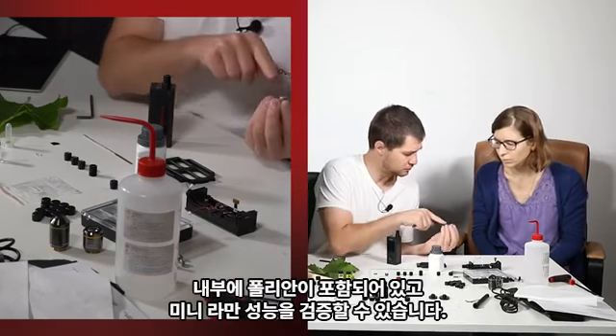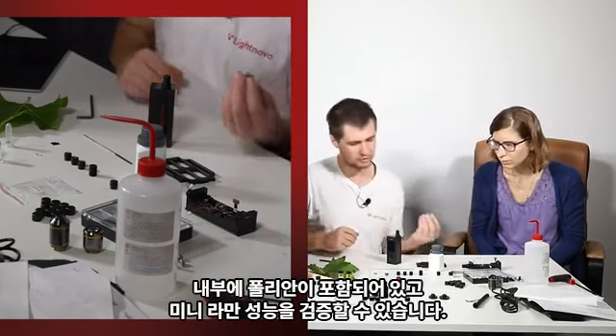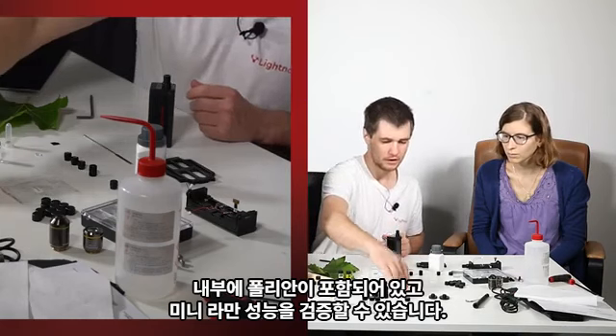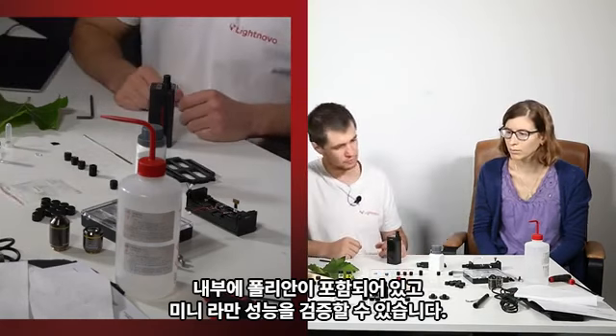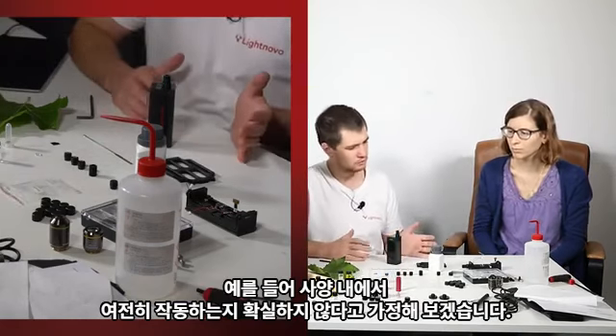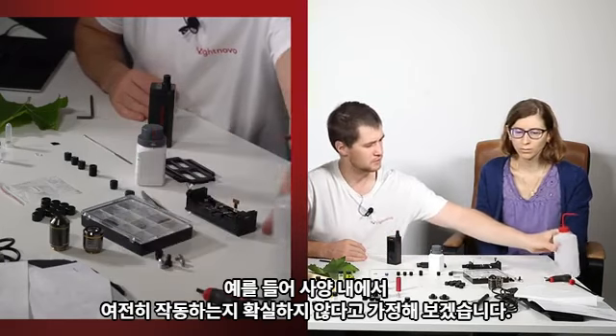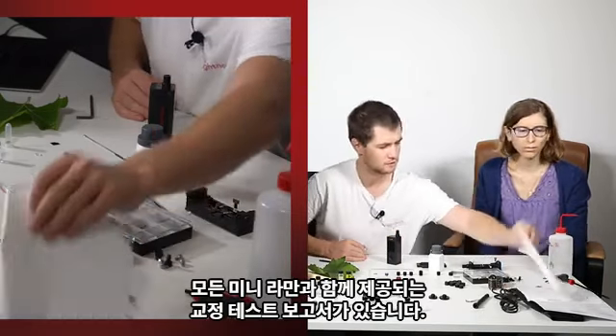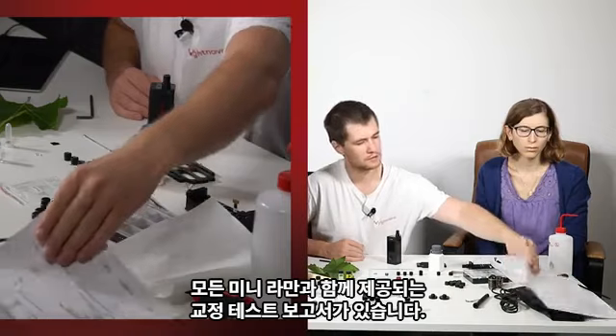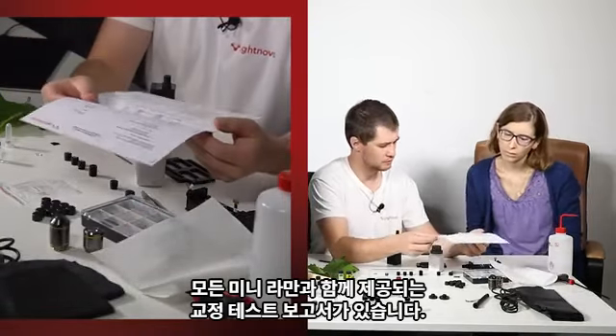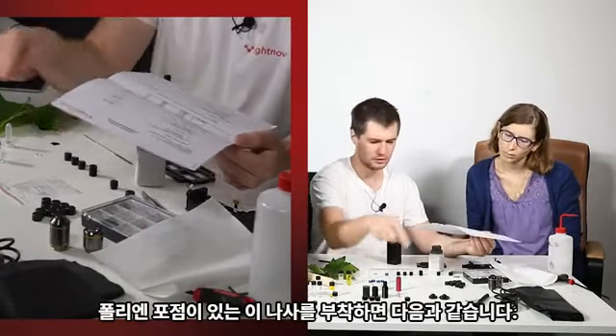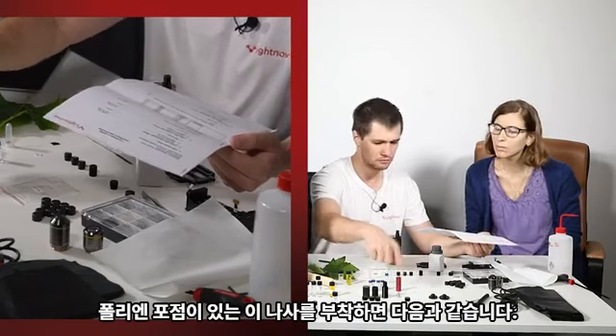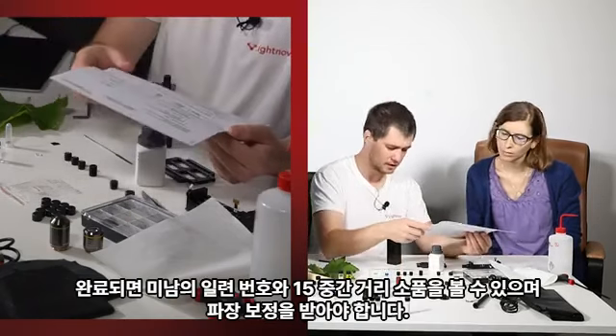This is one option. And by the way, this focusing stage comes with normal screws, or we have a special screw with polystyrene inside. And you can do verification of miniRaman performance. Let's say you are not sure if it's still working within the specifications. Then we have this calibration test report, which we supply with every miniRaman. You attach this screw with polystyrene in focus, and it is done.